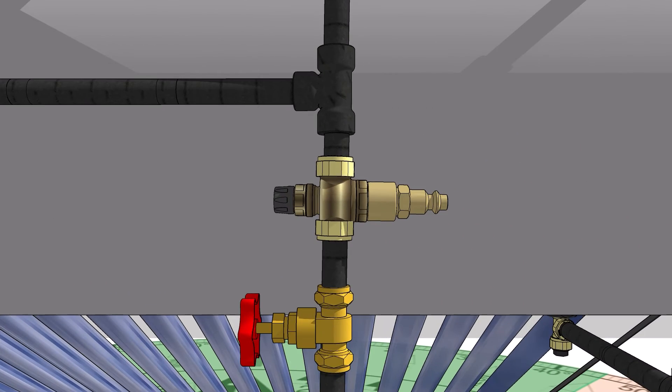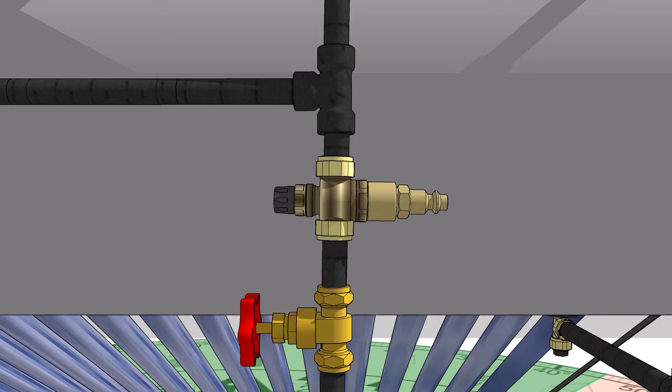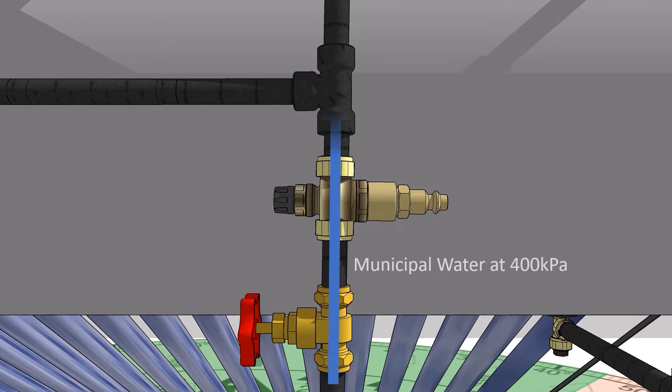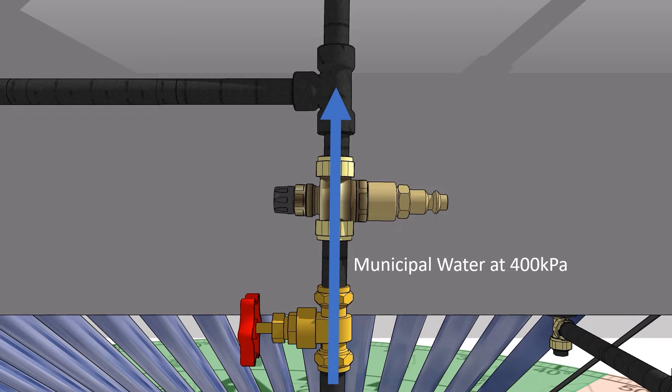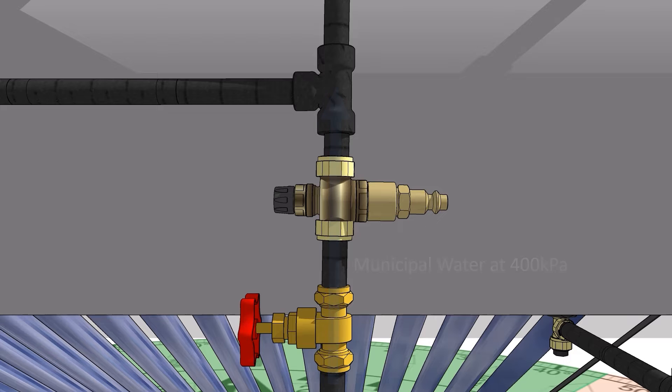400 kPa pressure control valve. Apollo solar geysers are rated 400 kPa. Therefore, a 400 kPa pressure control valve or relief valve must be installed along the cold water inlet pipe feeding towards the geyser.